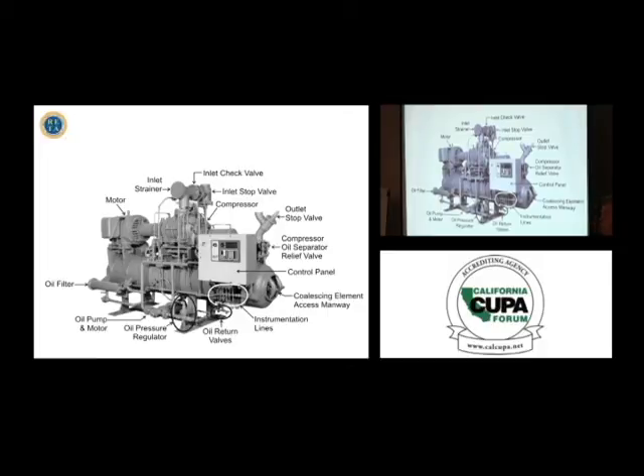You've got subcooled, you've got saturated, and you've got superheated. The refrigerant is always one of those three, and that's what I expect of you to learn as you become my operator: what is the condition out there, and is that the right condition? That's what you will eventually be trained up to do.